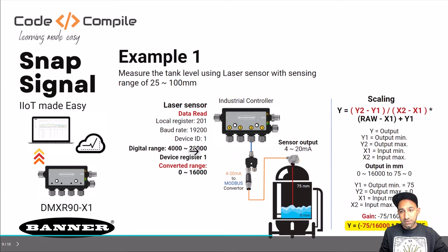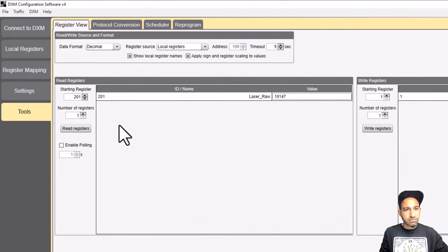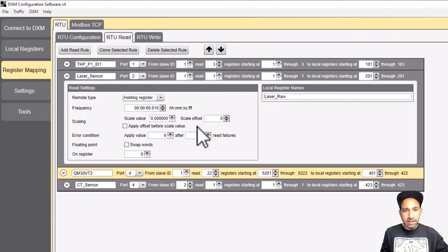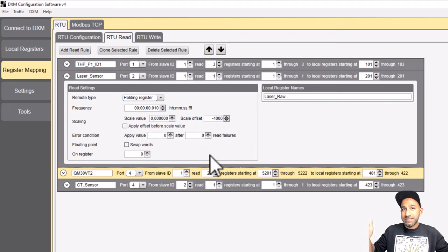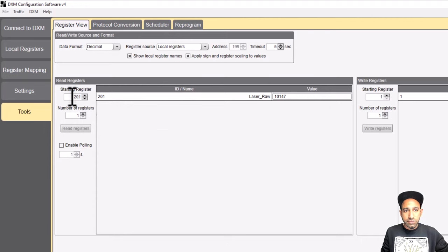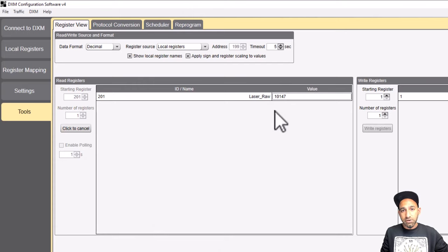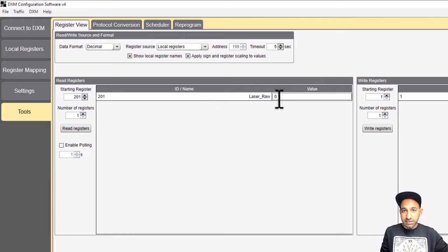In my example, the value ranges from 4000 to 20,000 and this should be converted to the tank level, which goes from 75 to 0 in inverse — because if the sensor gets less value, the tank level is increasing; if it gets more, the tank level is decreasing. To make scaling easy, I can add an offset of minus 4000 in the register mapping. This changes my range from 4000–20,000 to 0–16,000. After saving the configuration and sending it to the controller, the value now reads zero instead of 4000.